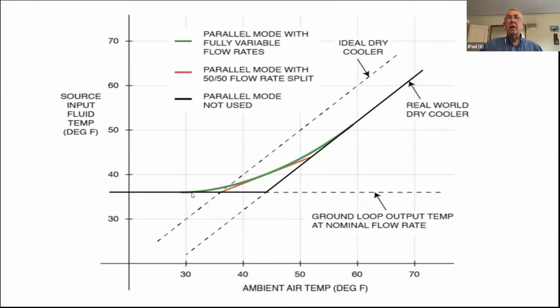So now, if we do not have the parallel mode, we would be coming along this horizontal line and we'd come all the way up to here. And then the computer would say, we're better off switching now to an air source mode. So then we'd move right up to here and we'd move up this line. And so now we're getting warmer and warmer temperature.